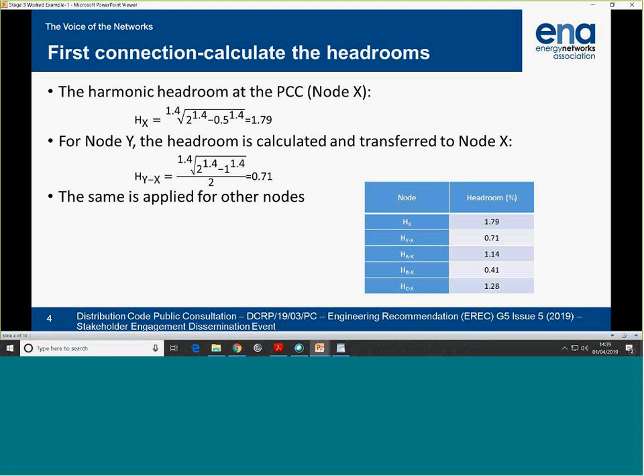First, I calculate the headroom at the connection point, X. Planning level minus the background in the table was 0.5 for bus bar X. It gives me a headroom of 1.79. The headroom available at bus bar X I can play with. And transfer coefficients from X to Y... sorry, the headroom is 0.71.